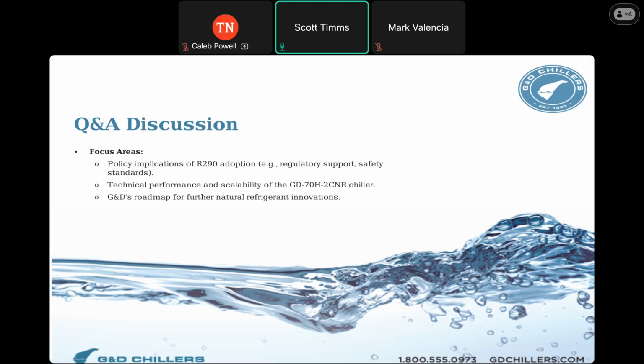Installation is important too. If you install your chiller too close to a wall, or a lot of times folks will actually install them backwards, where the outlet air is shooting straight into a wall, you're going to get recirculation of that hot air, which causes issues during hot months, and will also cause it to be less efficient even during cool months. So make sure the install is done correctly, insulate your pipes, and stay on top of cleaning the condenser, which is really, really easy.